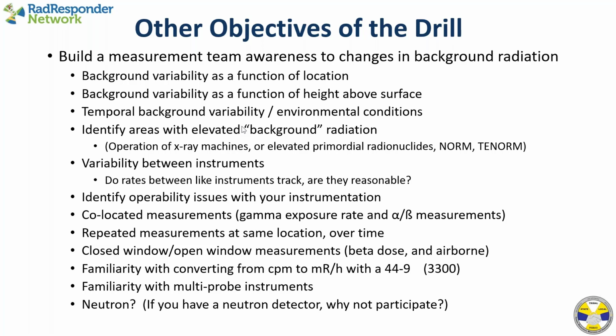Let's see, identify operability issues with your instrumentation, a great time to do that. I think I mentioned that earlier. Also, I probably should really have bolded this, co-located measurements. Especially when you get a region with elevated background, it's always informative to take a co-located measurement. That is, okay, I've got what looks like a high background area here from my sodium iodide Bicron or a plastic scintillation detector Bicron instrument.